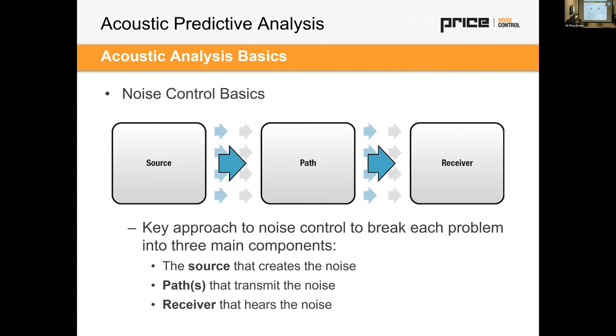The basics of noise control, and what myself and my team do a lot of, is basically break a problem down into its elements. There's a source of noise, a path, and then a receiver that need to be understood when you're performing an acoustic predictive analysis. Some situations are quite complicated: there's multiple sources, multiple paths, maybe multiple receivers. Others are quite simple, where you have one air handler feeding down into one space.